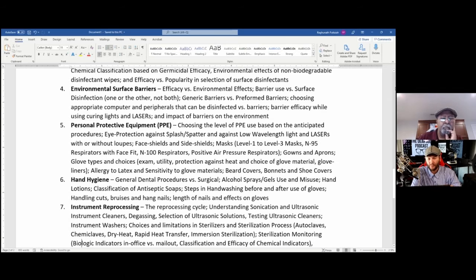One of the things I think people really need to know is that these indicators show something happened at some point during the cycle, not that the cycle was correctly done. Your indicator indicates one thing and only one thing, and that is whether it got up to a certain temperature, which is almost always dependent upon the pressure, because PV equals nRT, right? So basically, it's an indicator of only one thing, which is the pressure. If it didn't get up to the pressure for the right amount of time, it didn't get up to the temperature for the right amount of time, and you are never going to know if that pouch is truly sterile. You just know, in a snapshot in time, that it was at the appropriate conditions to become sterile if it remained at those conditions for 25 minutes.